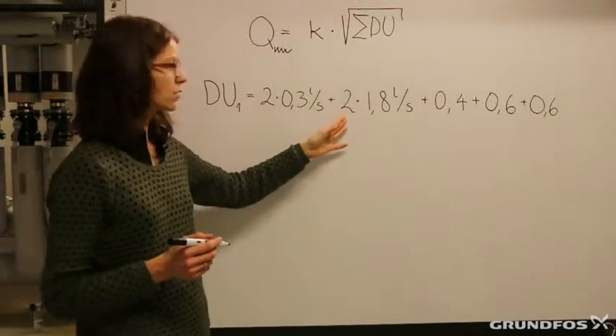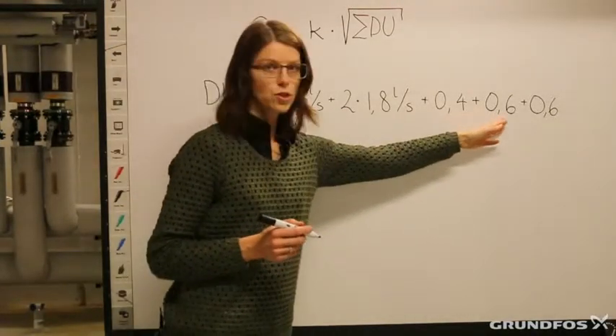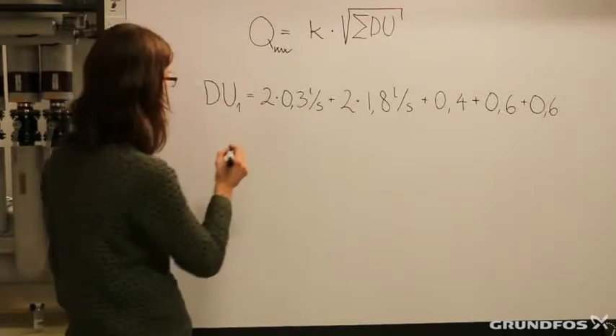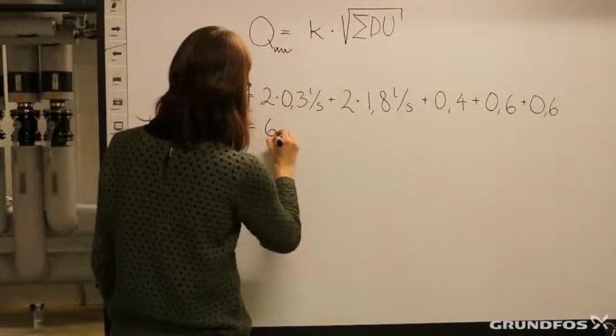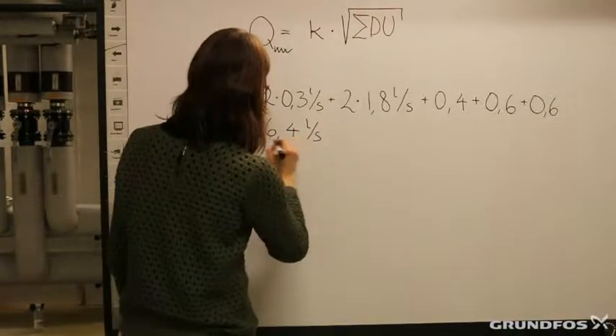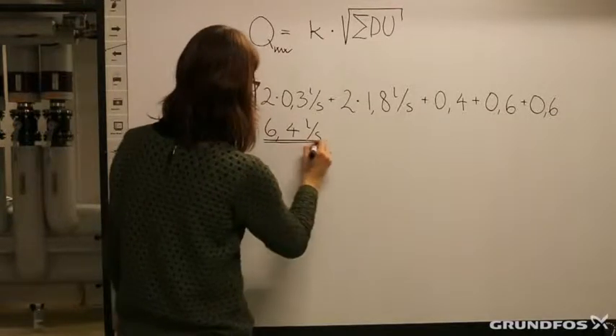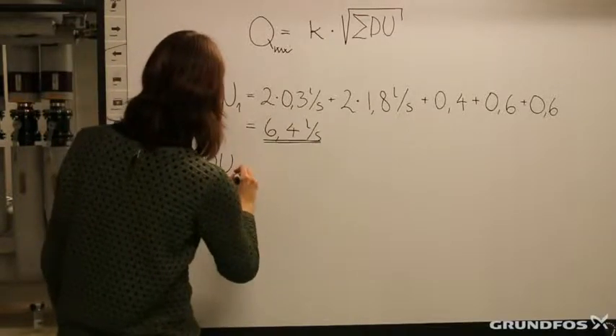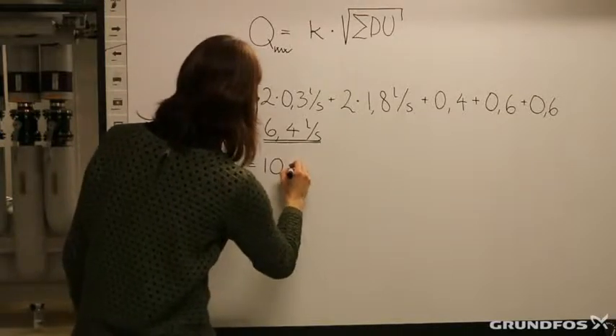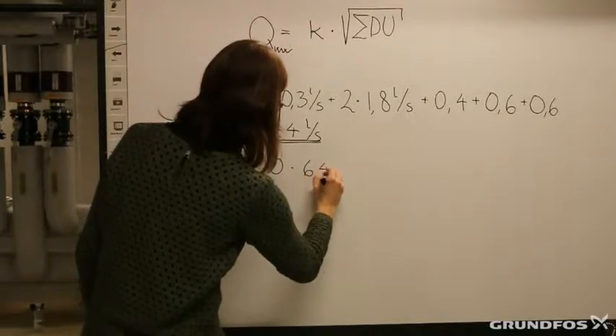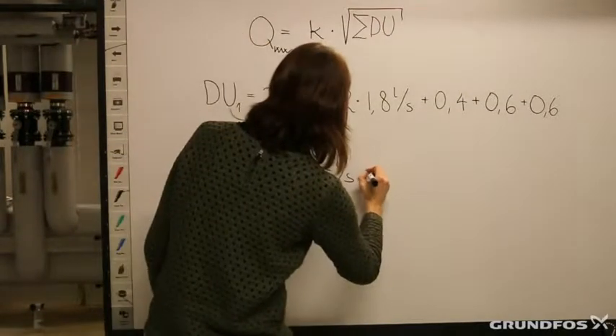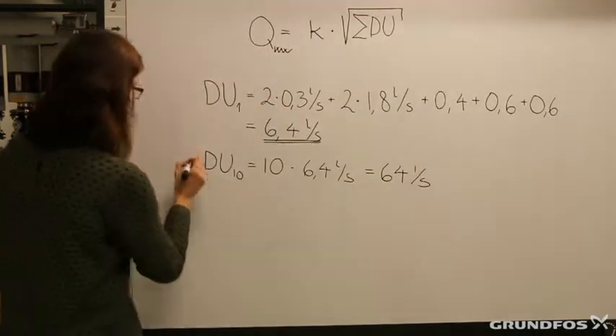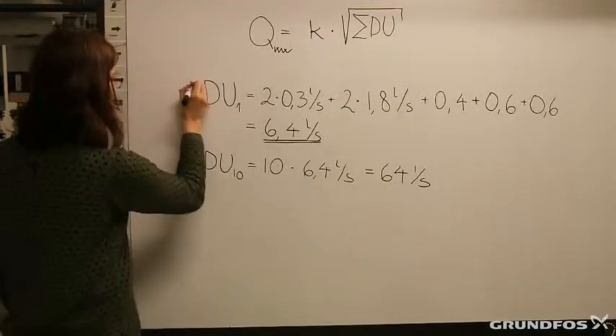First we will calculate the discharge flow from one dwelling. We have 2 washbasins, 2 toilets, 1 shower, 1 dishwasher, and 1 washing machine. The total discharge flow from one dwelling will be 6.4 liters per second. We have 10 dwellings, so the discharge flow from 10 dwellings will be 10 times 6.4 liters per second, which equals 64 liters per second. That's the sum of the discharge units.